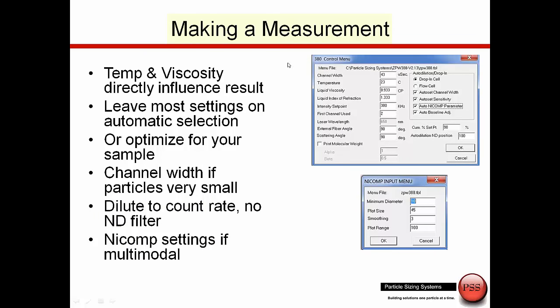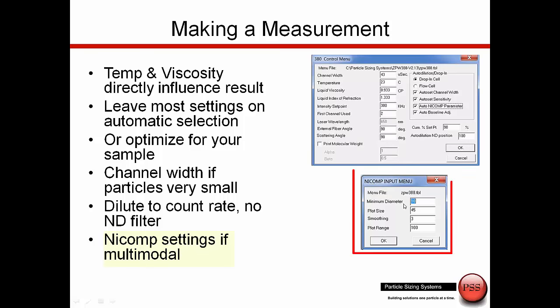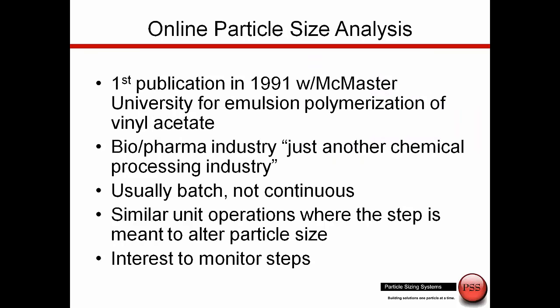As we look at the software and start setting up the system, let's look at how we specifically lock these things down. For temperature and viscosity, we input the values. The count rate we're going to set up to work near 300 kHz. We're not going to use the neutral density filter — we'll just control this by controlling the dilution. Channel width is something we typically leave in automatic, but we can reduce it if we know we're measuring very small particles. If we're going to use the Nicomp algorithm, we have access to the algorithm and it can automatically calculate the result. For online installations we've typically been working with the Gaussian, where the single result — typically the intensity mean diameter — is the value we use for process monitoring.